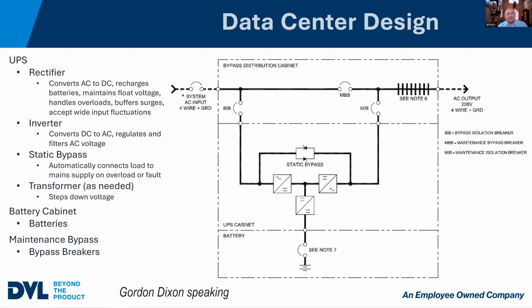The maintenance bypass is the third primary component. I say primary because there are other components as well, but maintenance bypass isn't always needed. It is almost always recommended though. What it allows you to do is take utility feed and pass it through without going to the UPS.